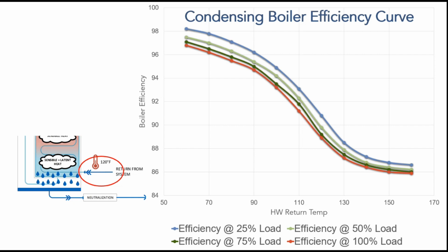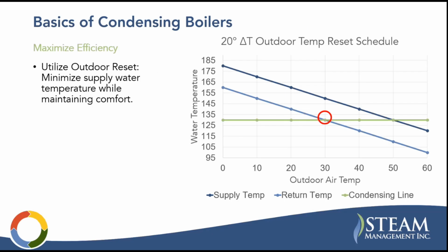So if you have a traditional hot water system and you actually have a set point requirement of 180 degrees at all times, your return temperature is probably not going to get down to where you can get into condensing mode, and you're not going to get the benefit out of that boiler. So we'll talk more about how to optimize that later.